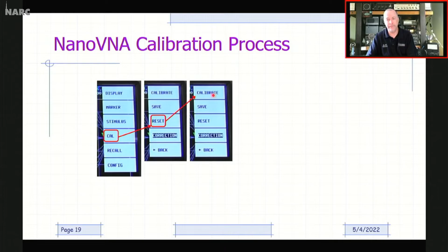Once you do that, it's going to prompt you to attach the various what are called calibration standards to the device or at the point where your DUT connects. And there's basically an open, short, and a load, OSL, okay? You connect the open, which just looks like, in this case, an SMA termination cap with nothing in the middle of it. It's literally just an open circuit, okay? And then you touch on open, you connect it, touch on open, it makes the sweep with that. Then you attach the short, touch on short, and then it makes the measurement on that one. Do the same thing for the 50 ohm load. So that will take care of those first 3 channel 0 calibrations.